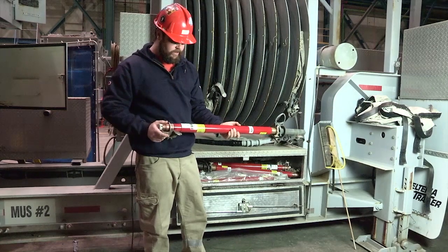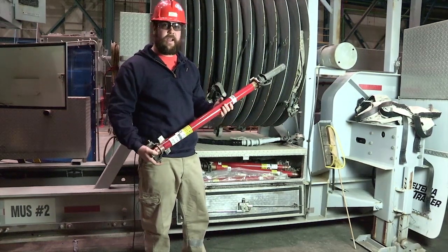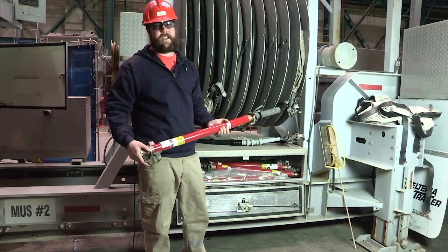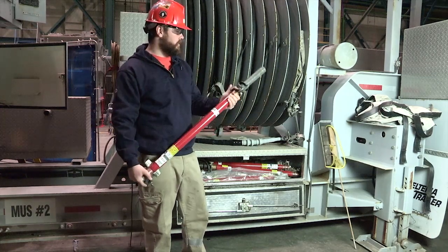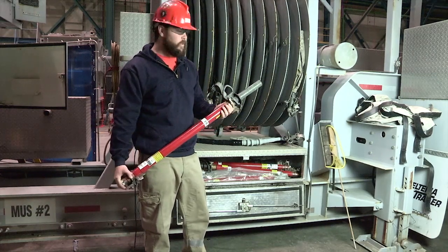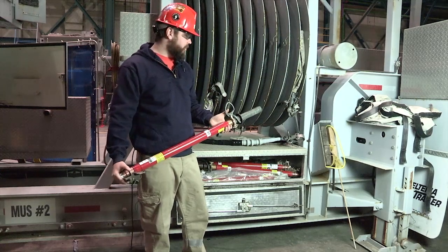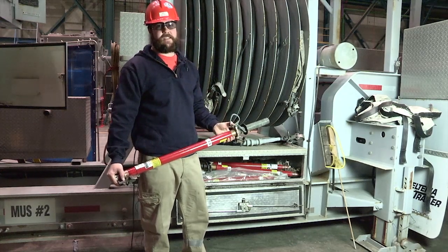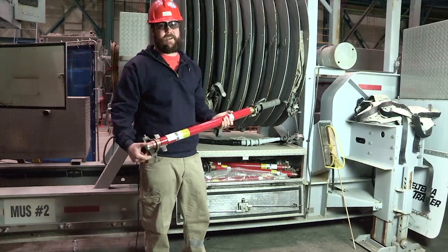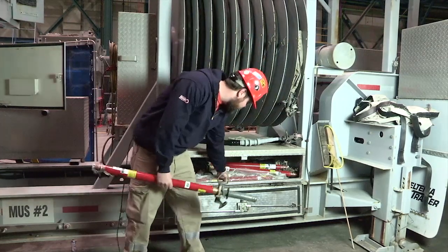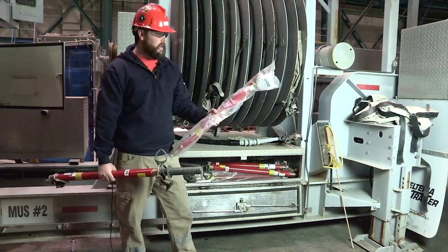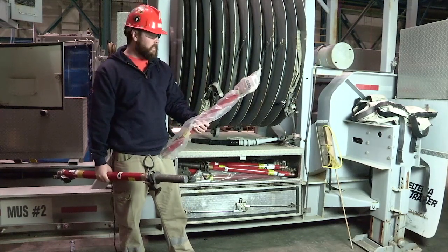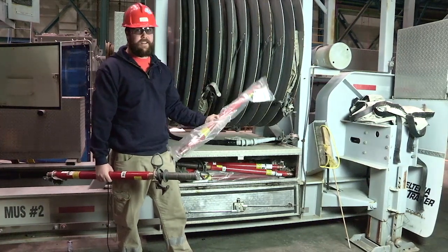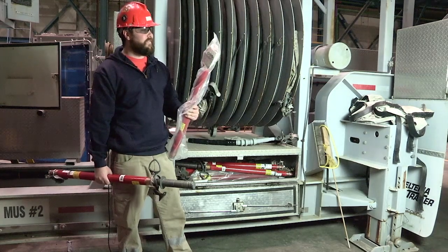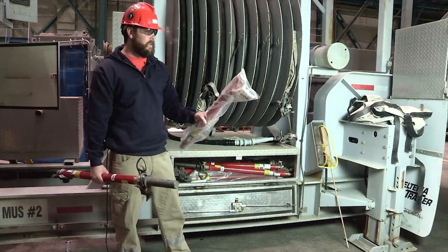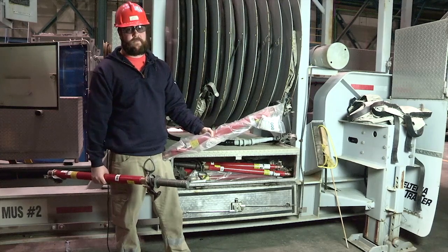And you also have to make sure that for every amperage you're carrying, at least carry 4 altogether. You have 3 and then an extra spare so you can dress any 3 fuses. And you usually like to keep between 100 to 200 amp high side fuses on it, depending on the MUS you have. And just to go through the compartment, bag the spares every year, because they get opened over time. Clean out anything that's left over. You get a lot of spares, weird sizes. You've got some 34.5s, 44 kV. Just clean them all out and put on what's needed.